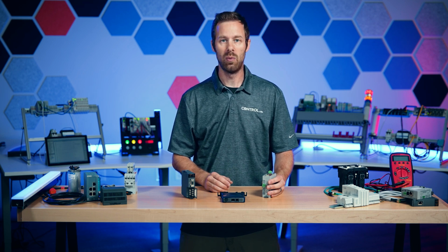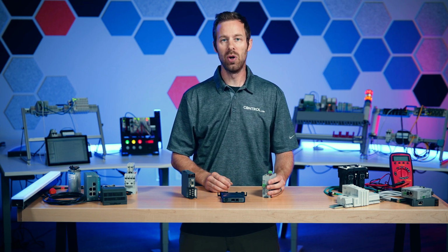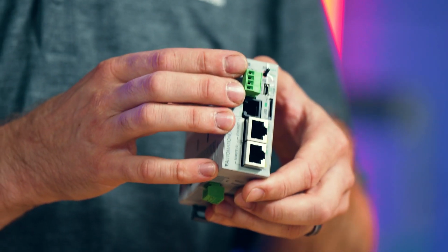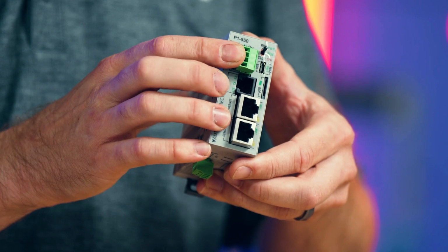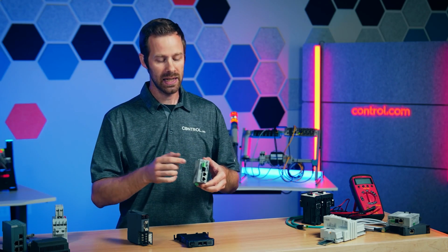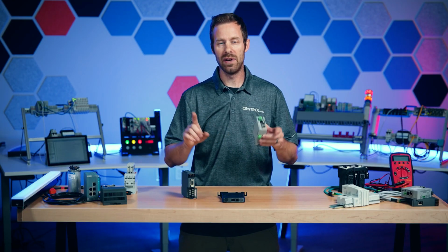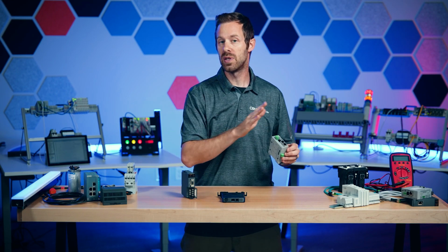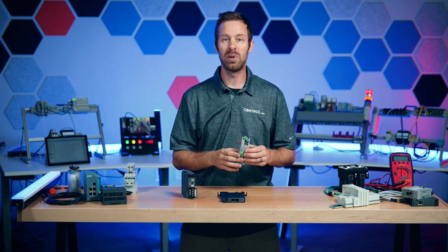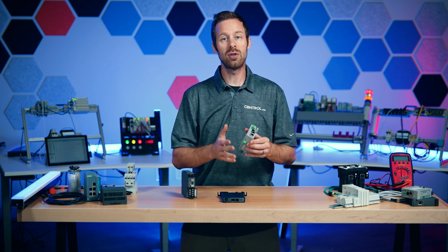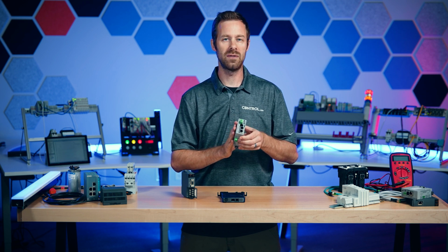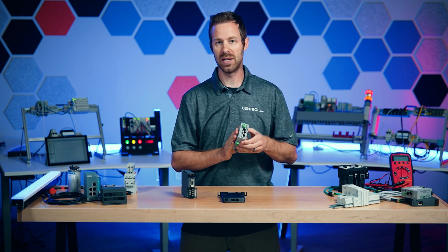RS-485, on the other hand, while it does transmit data, is a multi-drop type of system, which means that using positive and negative supply and a positive and negative communication supply, like a positive-negative voltage for a signal, can be attached across many devices. Now, one of the things that changes when you have a point-to-point interface versus a multi-drop interface, sort of like how we can think of Ethernet, is that since there's a lot of devices, the communication protocol needs to know which device it's talking to, which means addresses are important.